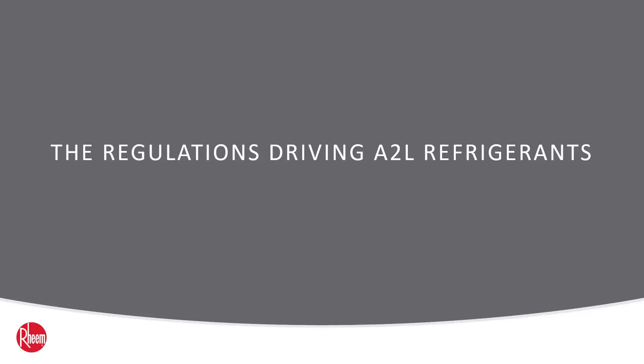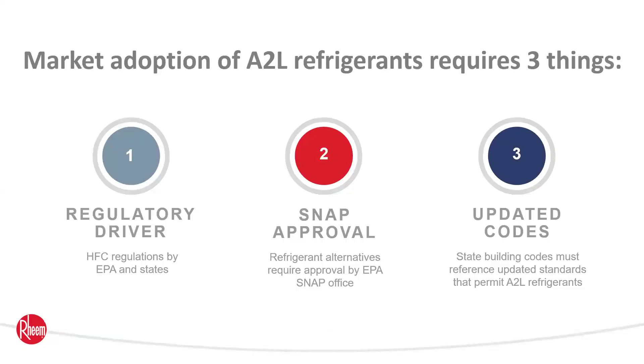You may have heard about A2L refrigerants for some time but wondered when they're actually going to arrive in the market. I like to describe broad market adoption of A2L refrigerants as requiring three things: one, a regulatory driver to require low global warming potential alternatives; two, EPA SNAP approval — the clearinghouse for refrigerant replacements by application; and three, updated building codes, because in order to install appliances containing flammables, codes must be updated to allow it.